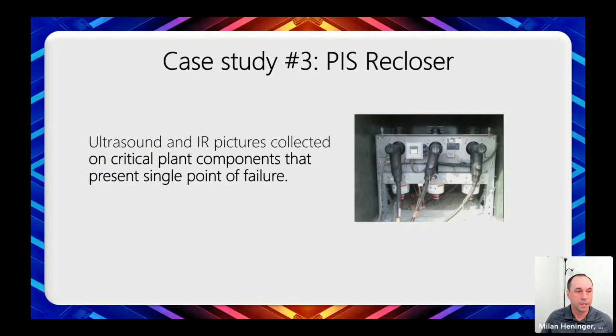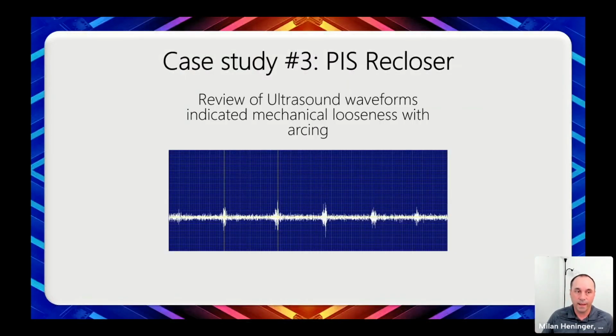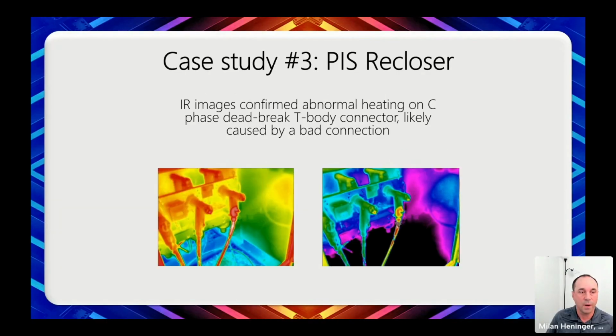Here on a recloser at a different facility, we once again did ultrasound and IR, and the ultrasound waveforms again indicated mechanical looseness with arcing. In this case, it was a little unusual. On the T-bodies, on the thermography, you can see that there's some heating that was occurring right where the connection with the wire and the T-body occurs. We knew that there had to be something wrong with this.